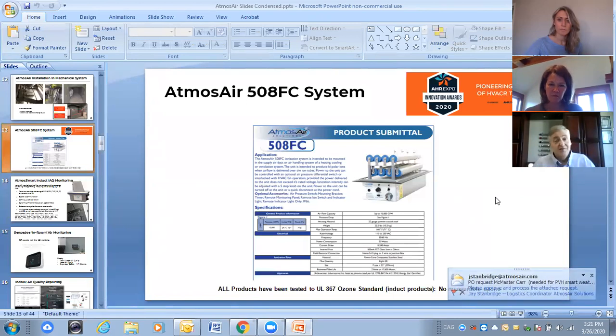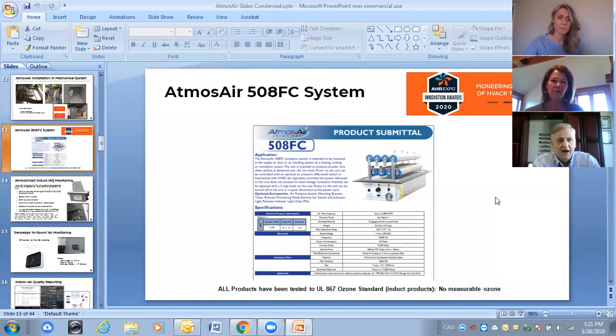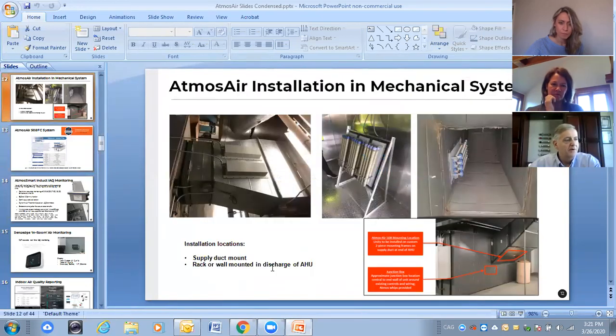How they're applied is simple, and I can say that because I'm able to install one of these systems myself. You cut an access into the supply side of the duct where the supply air is, and insert the unit's tubes into the airflow. If you look at this unit in the picture, there's a little flange on it. The chassis stays outside the duct, where the electrical and control connections are made, but the tubes go inside the duct where the air is flowing.